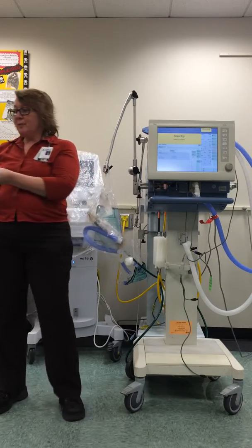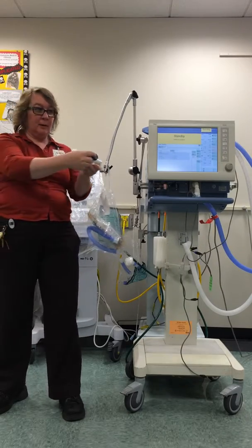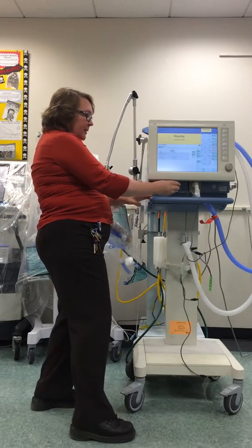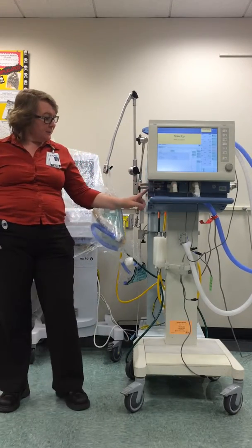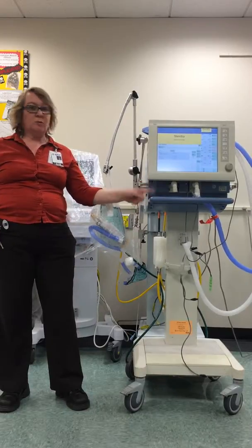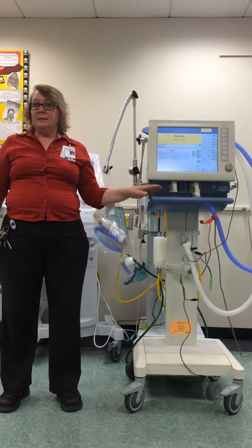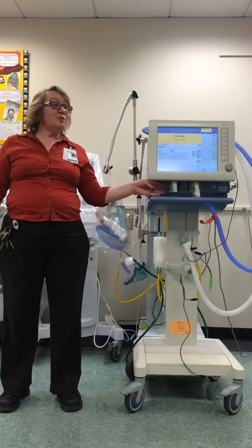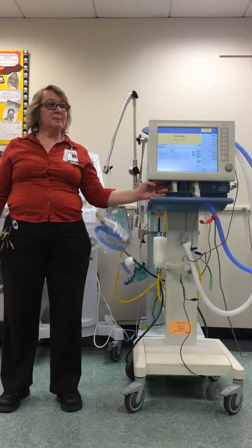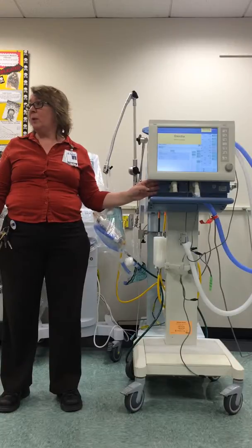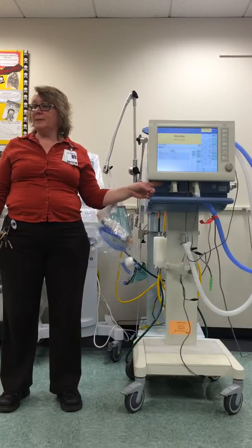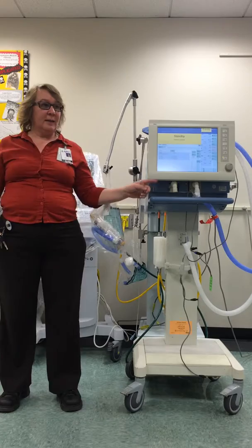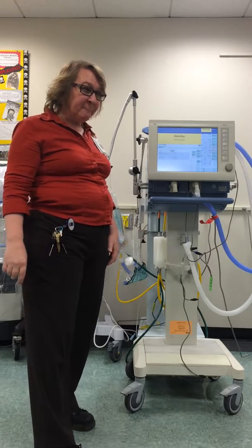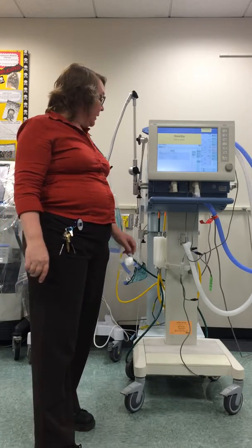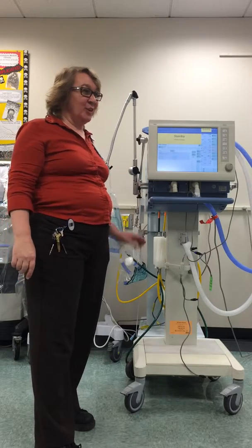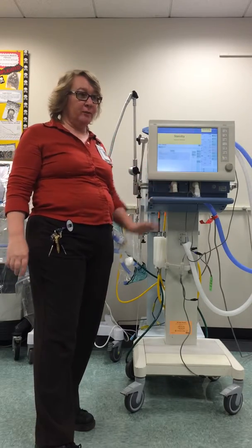So this is where your flow sensor is actually sitting, this little spot right here. So I'm going to put it back in, and it just literally snaps back into place. That will slide in, and the door will close. This is things that are all going to be there, but it is troubleshooting that has to be done, especially in a hospital when these are being used all the time, so that's why you need to be aware of those. Flow sensors break, exhalation valves break, so that's where those are. If the flow sensor isn't pushed into the exhalation port, will the flap close? It will close and it will not work. So you have to make sure that it slides all the way over.